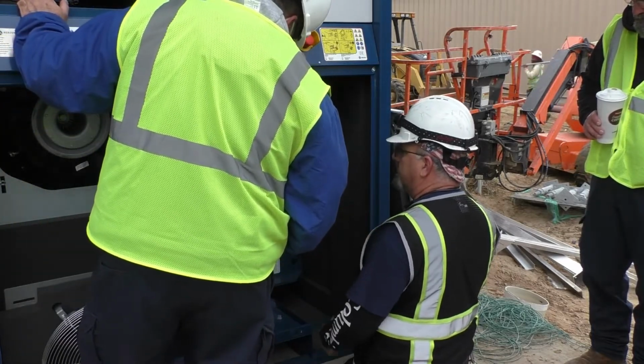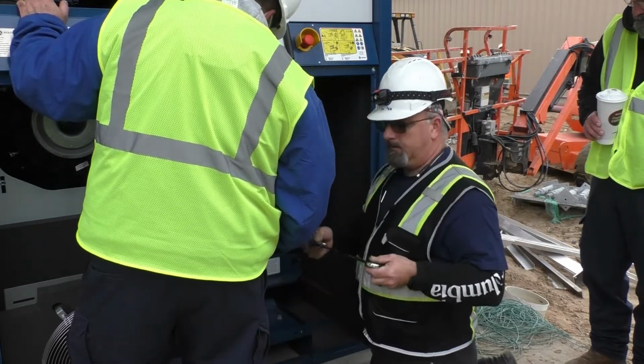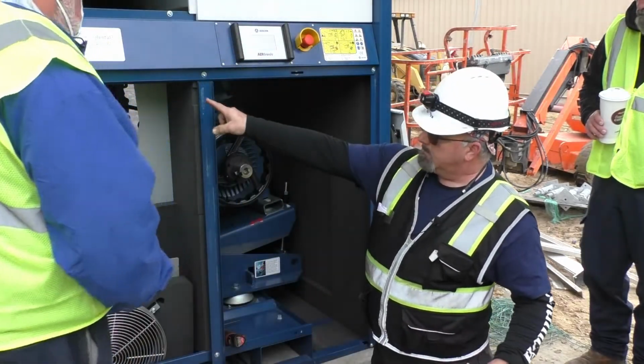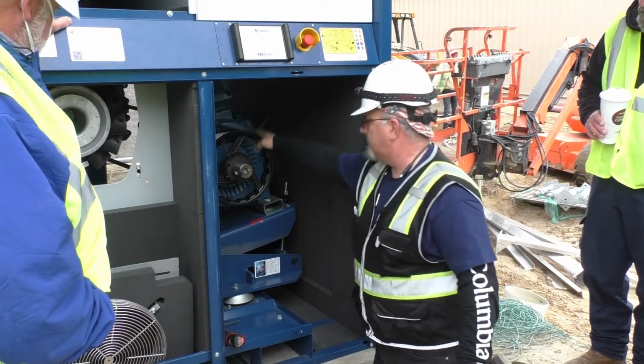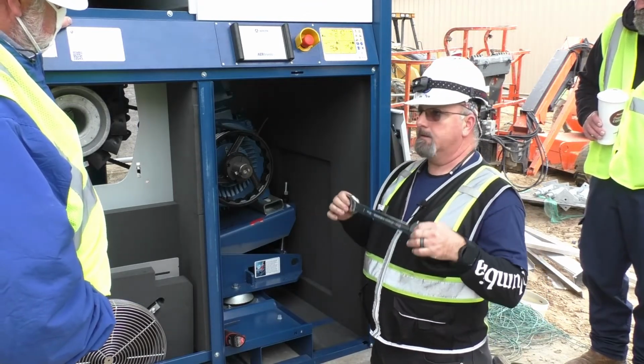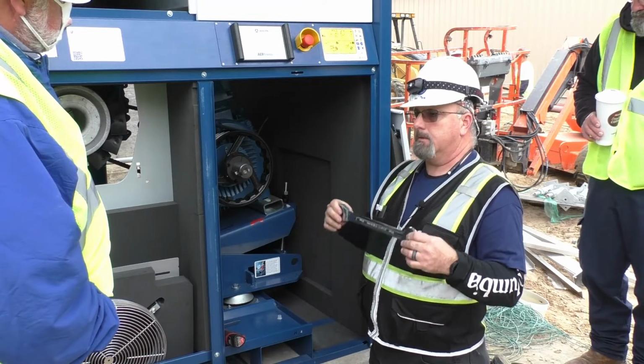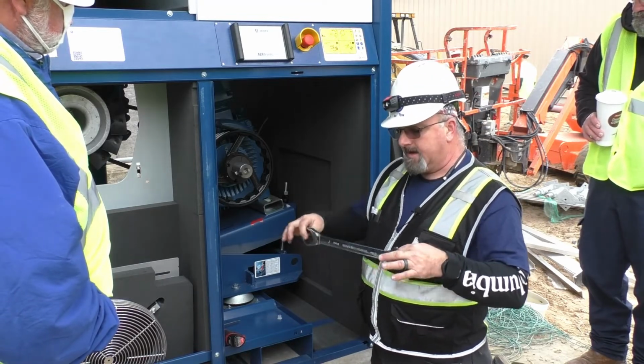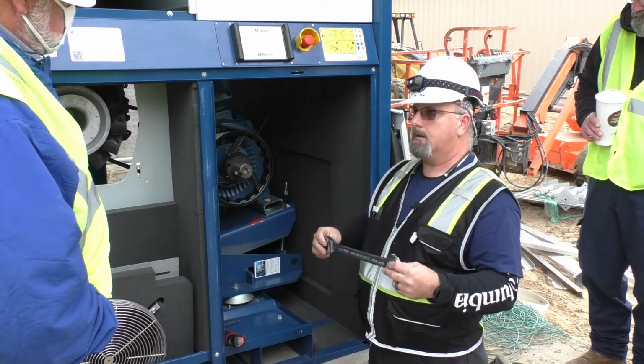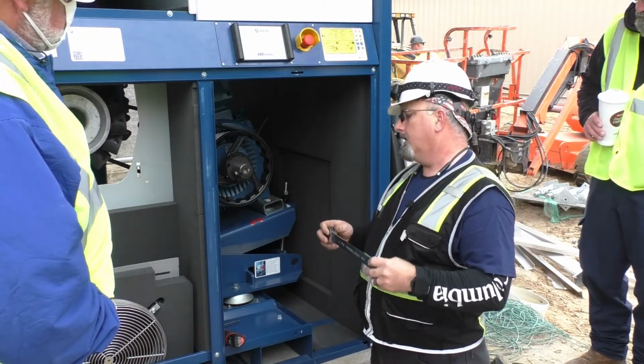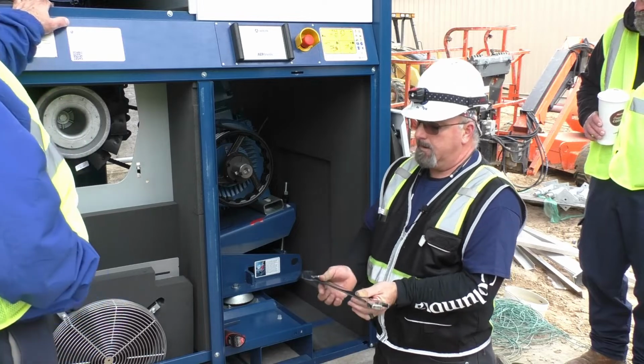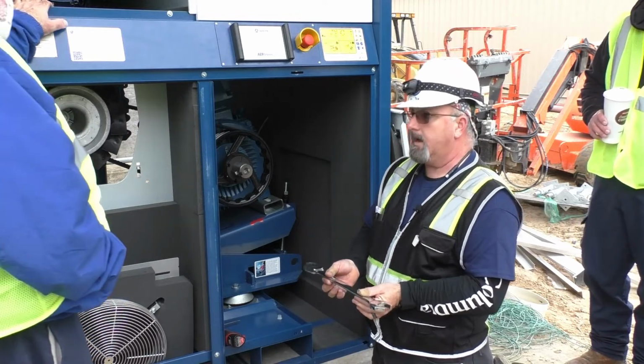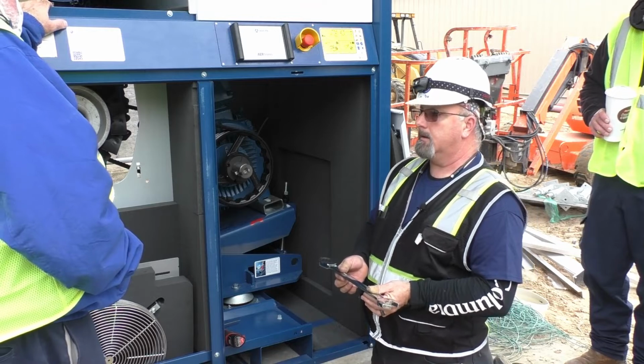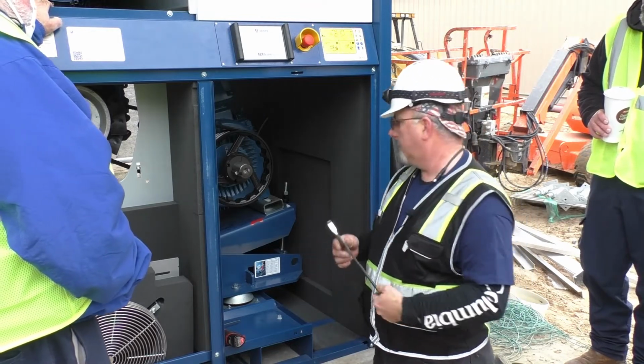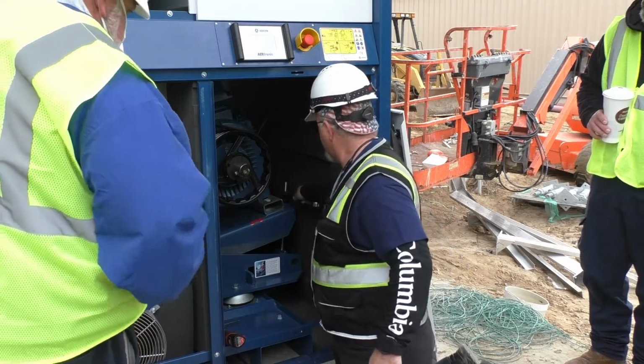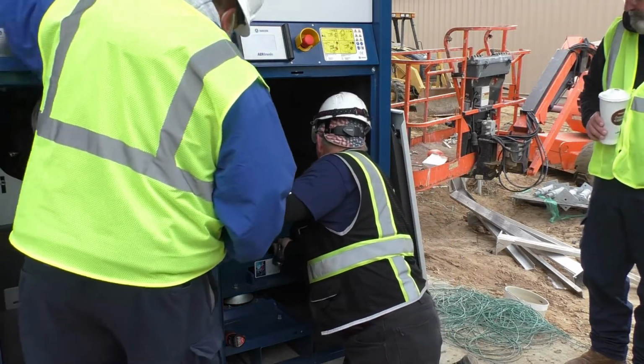With this, it alleviates, because if you're doing a manual tension, right now the sheave on the blower and the sheave on the motor, they are perfect. I used a laser alignment tool for belt drives to align those. So axially and horizontally, they are lined up to where they're running true. Whereas if you had the manual tension bolts, where you have one bolt over here and one over here, you would have to make sure you had that lined up, or you could create belt drive issues. So there is a way to, if they happen to get out of alignment.